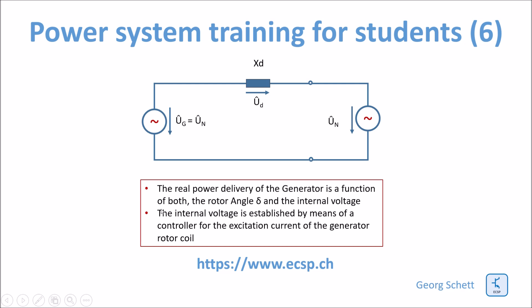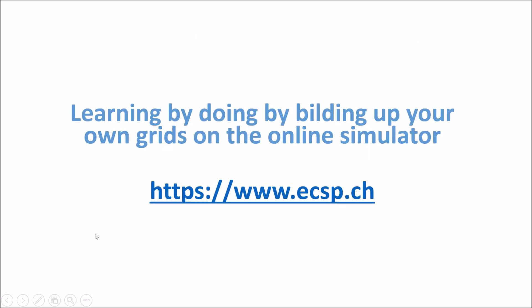The real power delivery of the generator is a function of both the rotor angle and the internal induced voltage of the generator. The internal voltage is established by means of a controller for the excitation current of the generator rotor coil. As usual, you can go to the simulator and build the case and try it yourself to get some hands-on experience — that's good for learning practice.